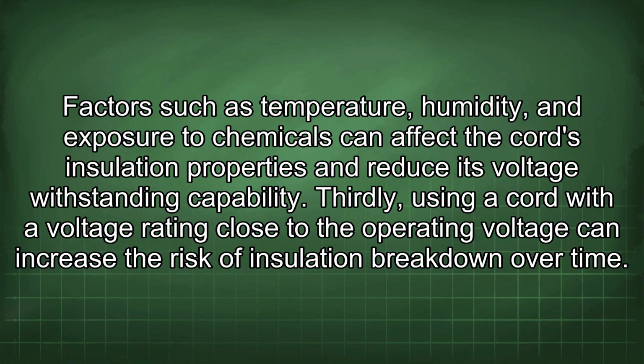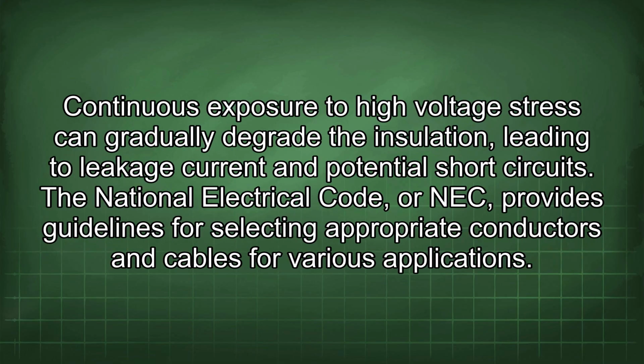Factors such as temperature, humidity, and exposure to chemicals can affect the cord's insulation properties and reduce its voltage withstanding capability. Thirdly, using a cord with a voltage rating close to the operating voltage can increase the risk of insulation breakdown over time. Continuous exposure to high voltage stress can gradually degrade the insulation, leading to leakage currents and potential short circuits.